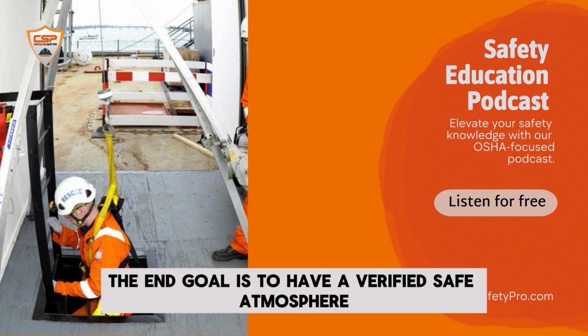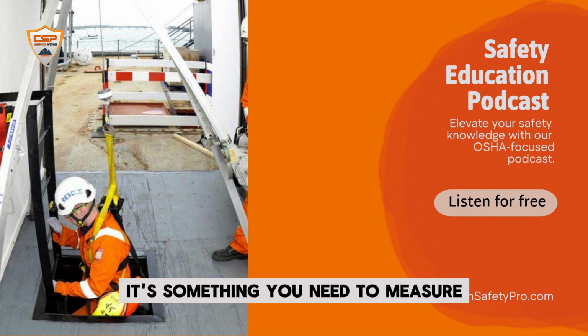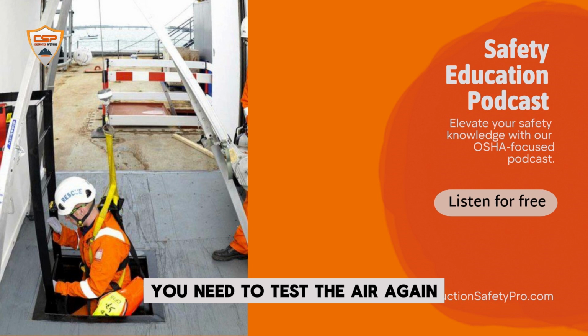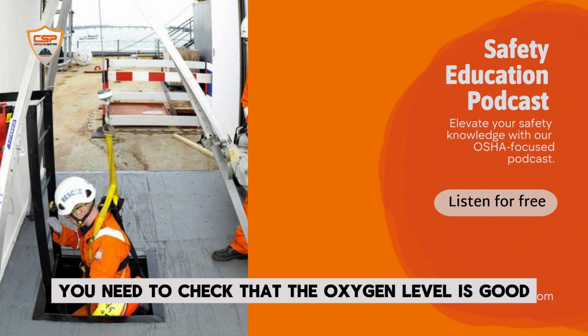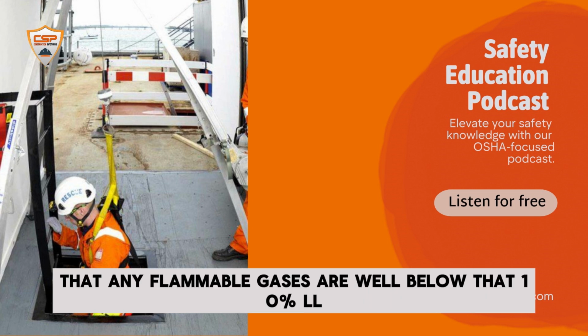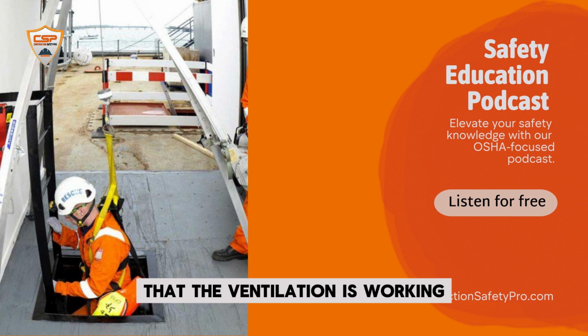The end goal is to have a verified safe atmosphere. And that's not just a feeling, it's something you need to measure. After you've run the ventilation for a while, you need to test the air again with a calibrated gas monitor before anyone goes in. You need to check that the oxygen level is good, that any flammable gases are well below that 10% LEL mark, and that any toxic contaminants are below their limits. Those readings are your proof that the ventilation is working.